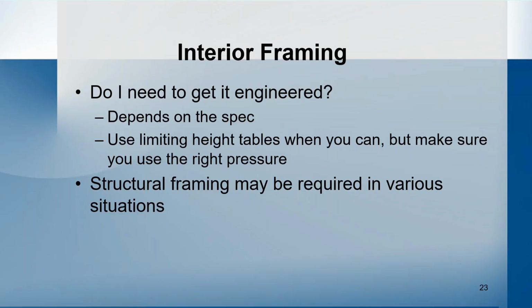So onto the interior framing portion. As we're seeing more frequently, not just in data centers, it's a common question of whether or not I need to get it engineered. A lot of times, it depends on what the spec says. Sometimes you can use limiting height tables, but you need to make sure that you're using the right pressure. For data centers, your pressures can be wildly different. It's not always the standard 5 PSF that you're used to with interior framing. We often see 10, 15, and even 20 pounds per square foot for an interior pressure.